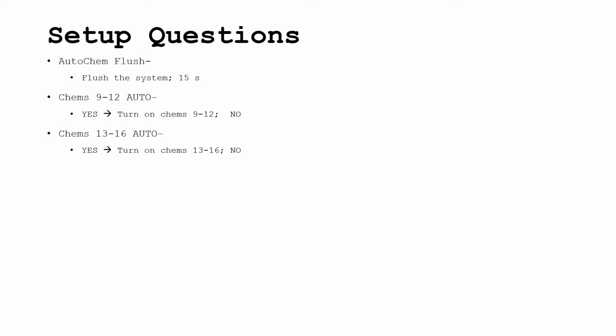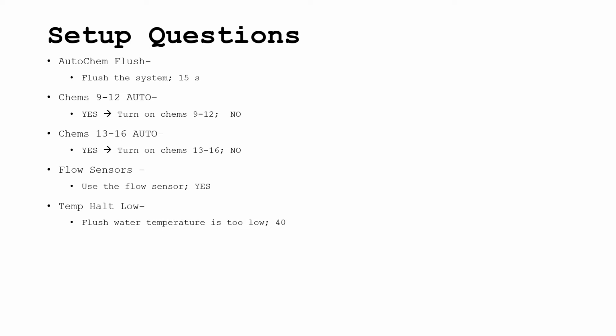Recommended, no. Flow sensors: tells the system to use the flow sensor input. This should be set to yes. Temp halt low: tells the system when the flush water temperature is too low, recommended, 40. Temp halt high: tells the system when the flush water temperature is too high, recommended, 120. Chemical watchdog: the maximum system inject time, recommended, 2 minutes.